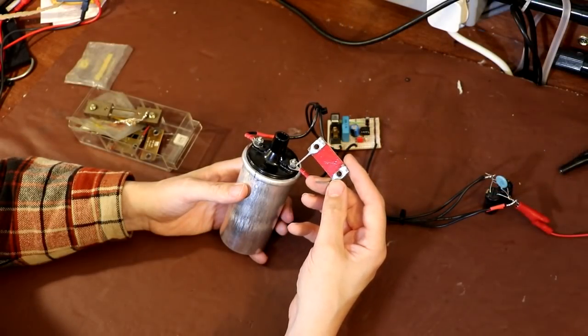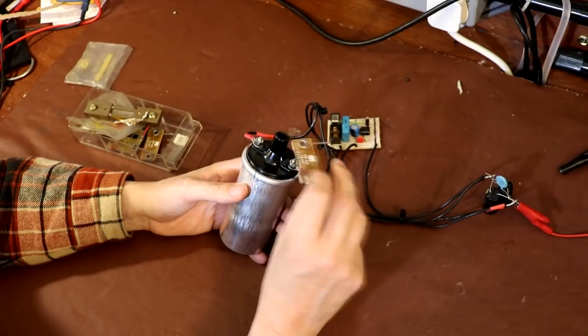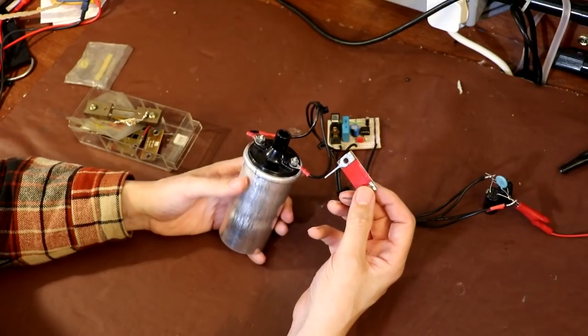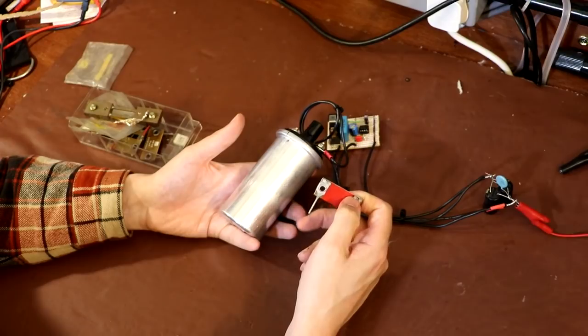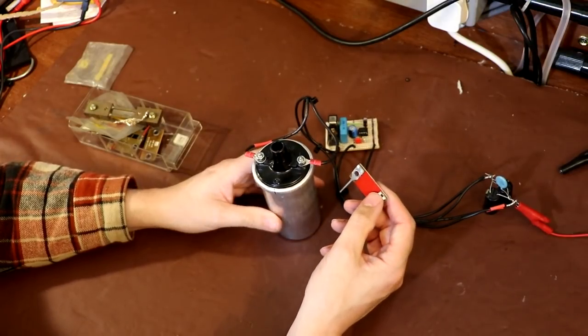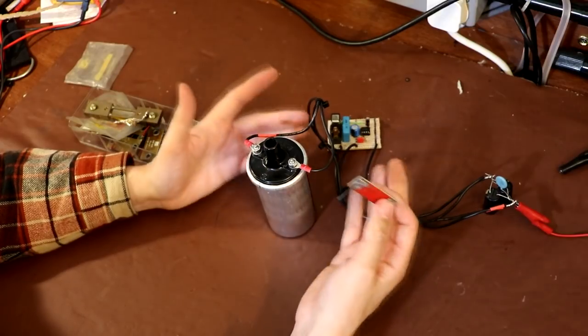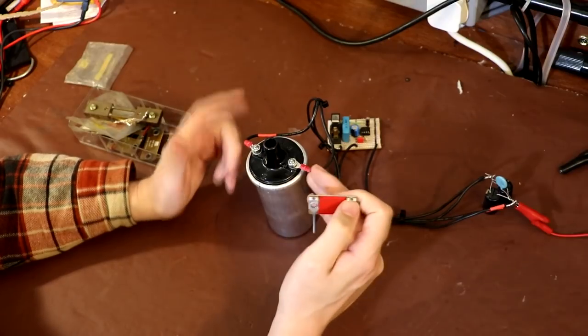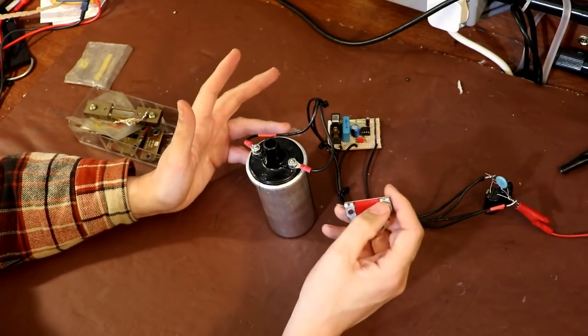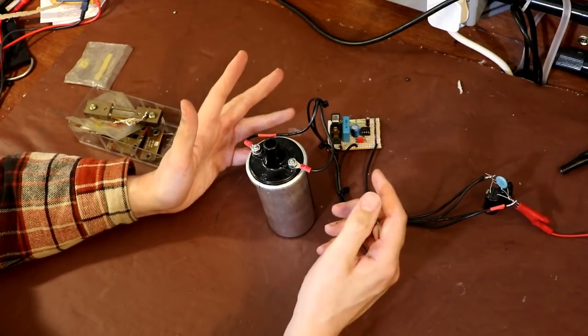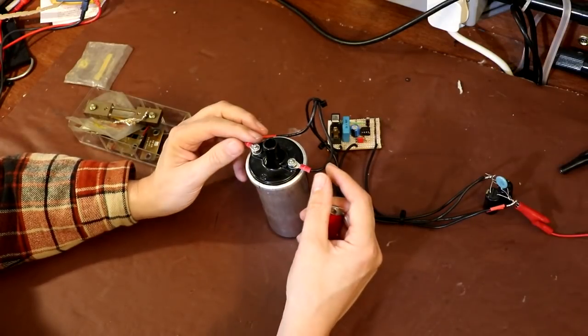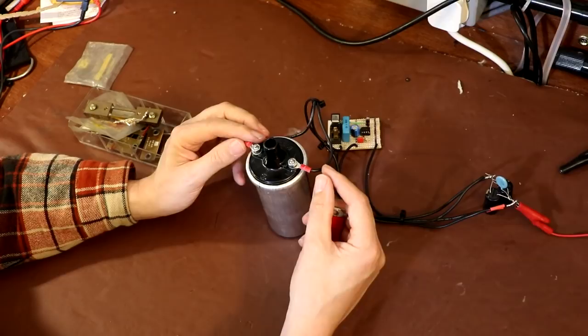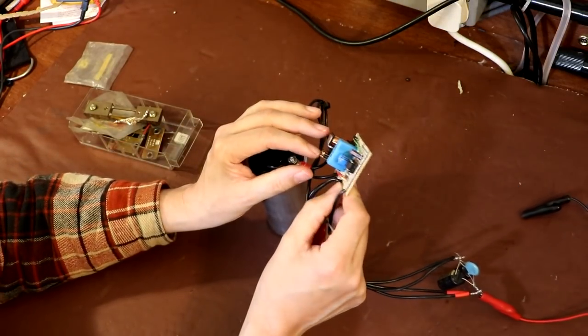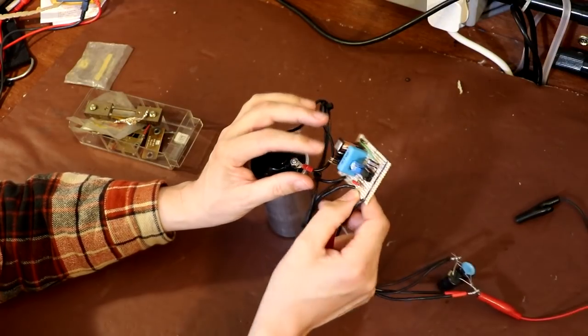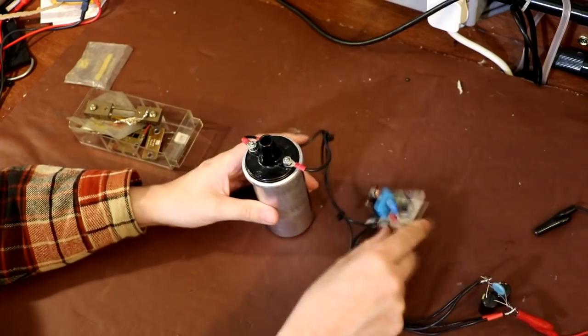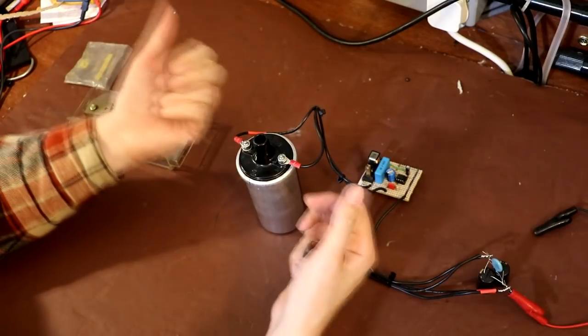We could wire in one of these current shunts to take a current measurement, but it probably wouldn't be my preferred choice. That's because large inductive loads like this can produce quite high voltage transients, or back EMF. When this coil de-energizes, when we turn the current off, it tries to maintain constant current through it by increasing the voltage. That's why you get a bit of a spark across the relay contacts, and it's what the capacitor is designed to prevent. So because it's an inductive load, you get a spike, a back EMF.